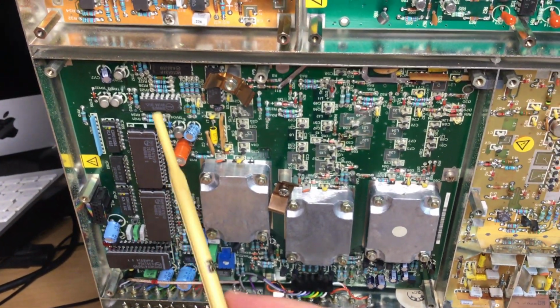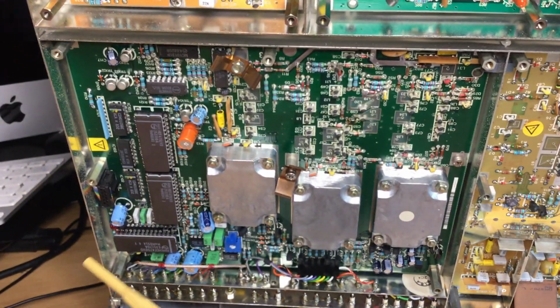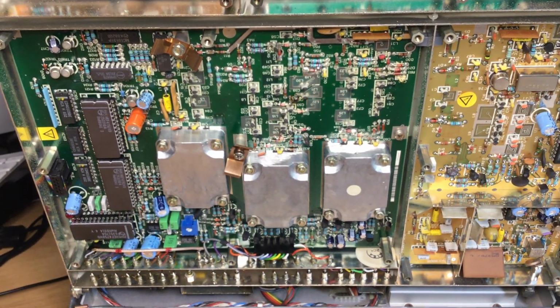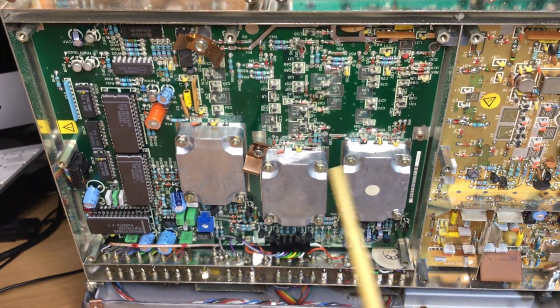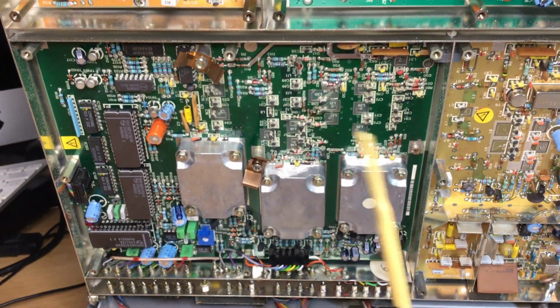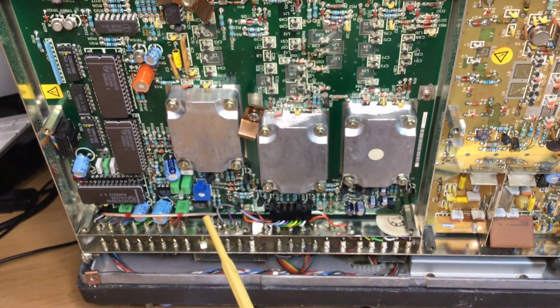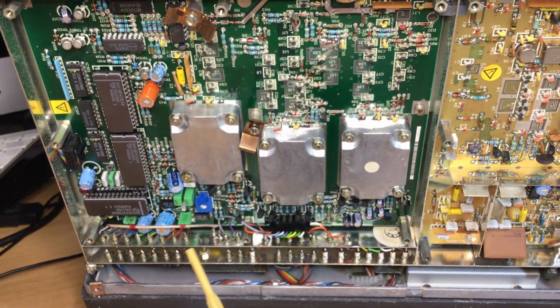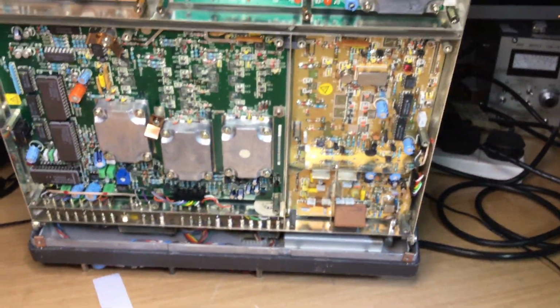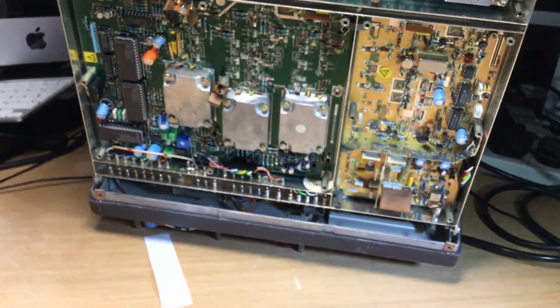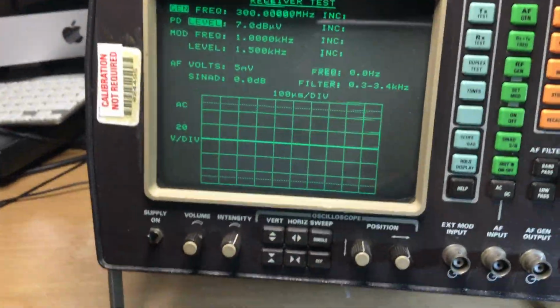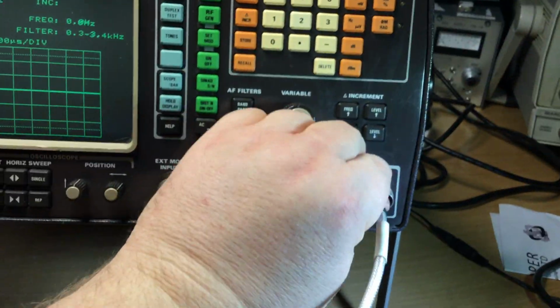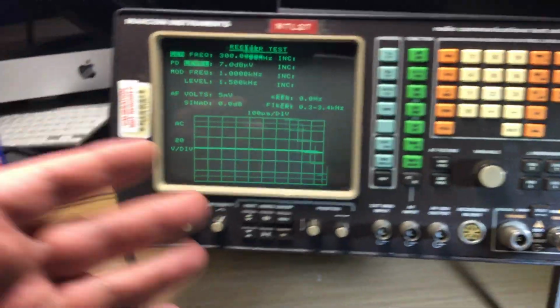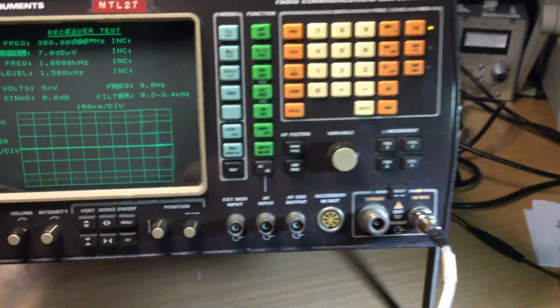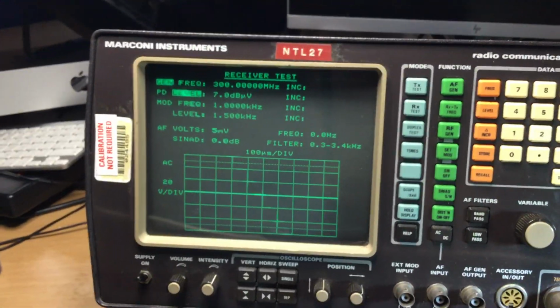These are the synthesizer chips, programmable dividers, VCO control, which then obviously these control inputs are fed to the digital circuitry board, the digital processor board, which then, as you enter the test frequencies on the front panel, will set this up to produce the right frequency. Again, we've got another potentiometer here for some calibration of the settings as well. So that's a little rundown of that bit. So yeah, if we were to do some testing, for example, to have a look at how good its calibration is, we can do that by connecting up another test set, or separates if you've got a signal generator, or a separate mod meter, a SINAD meter. You know, you could have lots of separates, for example, or you could just have a test instrument.